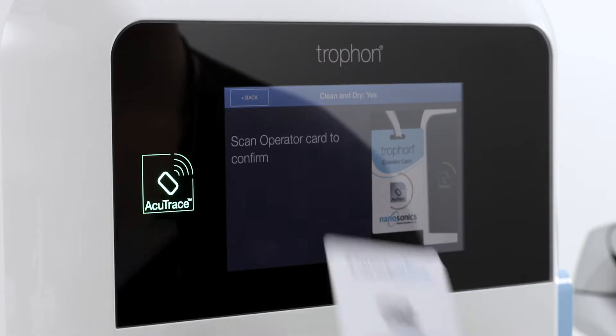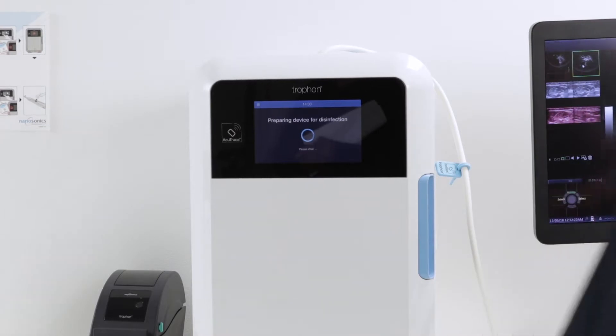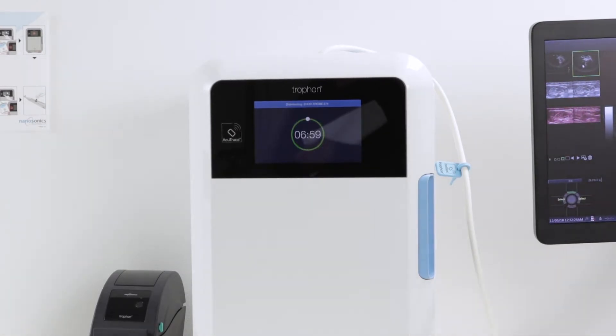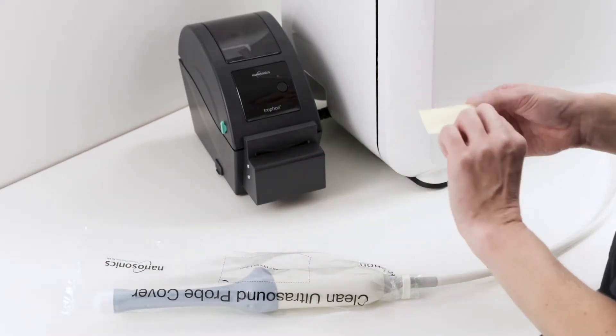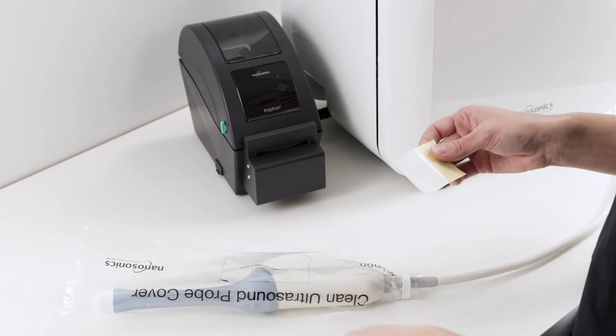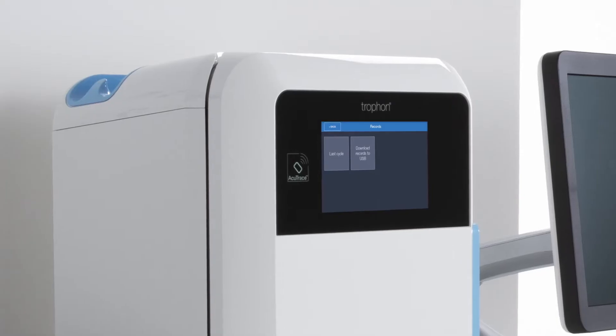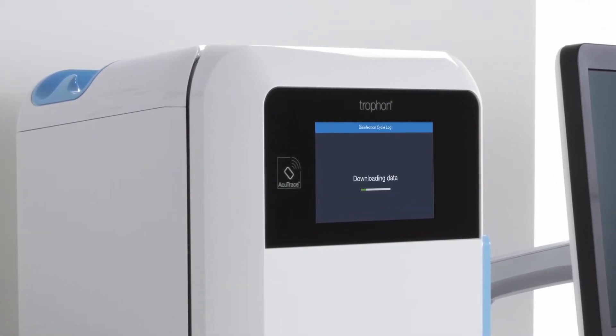AcuTrace simplifies the creation of accurate, audit-ready digital disinfection records and stores over 100,000 records directly on your trophon2. If you have the trophon printer installed, information on the disinfection cycle can be automatically printed out on up to four labels. One printed label can be placed on the Trofon Clean Ultrasound Probe Cover or in the patient's medical record for traceability. Alternatively, the disinfection records can be downloaded onto a USB for record keeping.